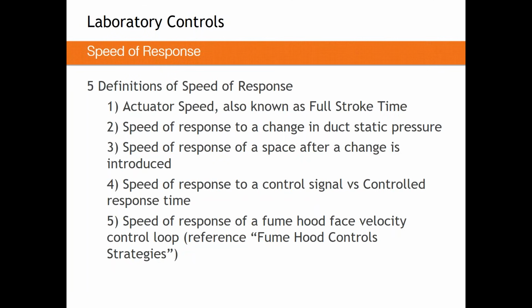The next type of speed of response is the speed of response of a space after a change is introduced. So in the lab environment, ANSI Z9.5 actually gives us a number for this, and it's 10 seconds. From the time you make a change, so whether you open and close a door or open and close a fume hood, for example, your room has 10 seconds or less to get back to the proper pressurization.